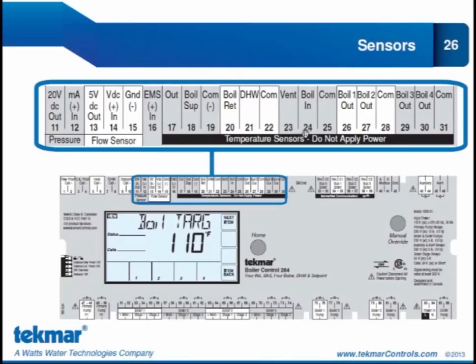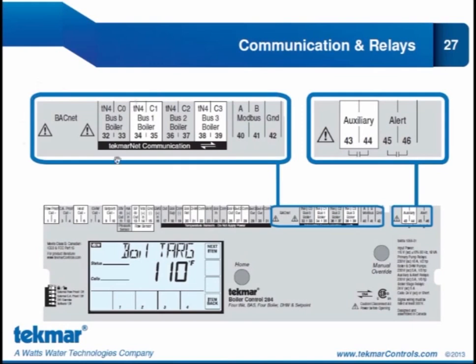We have a terminal for the vent sensor that we talked about, the boiler inlet sensor, and then there is an option to connect a boiler outlet sensor for each of the 4 boilers. For communication, you can see we have our BACnet connection over here, and that would be the RJ45 port at the top. And we have our Modbus communication terminals over here. As discussed, there are 4 TN4 buses. We have bus B, bus 1, 2, and 3. Now, it says clearly they are all boiler bus, just so there's no confusion. We cannot have any mixed buses on the 284. They all have to be boiler bus, but because we have 4 buses, we can connect up to 96 devices. We could also use these terminals to connect to a gateway control as well.